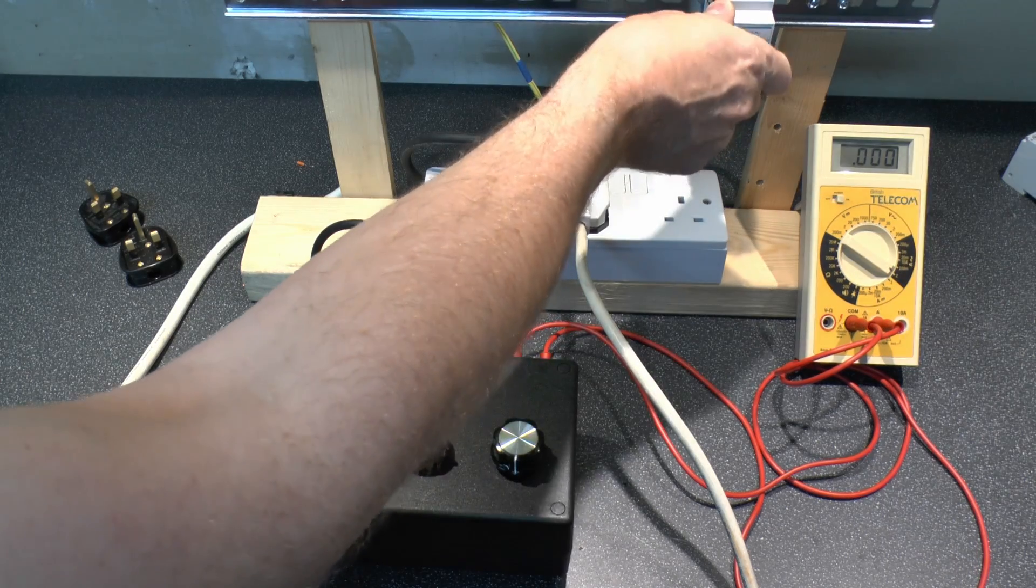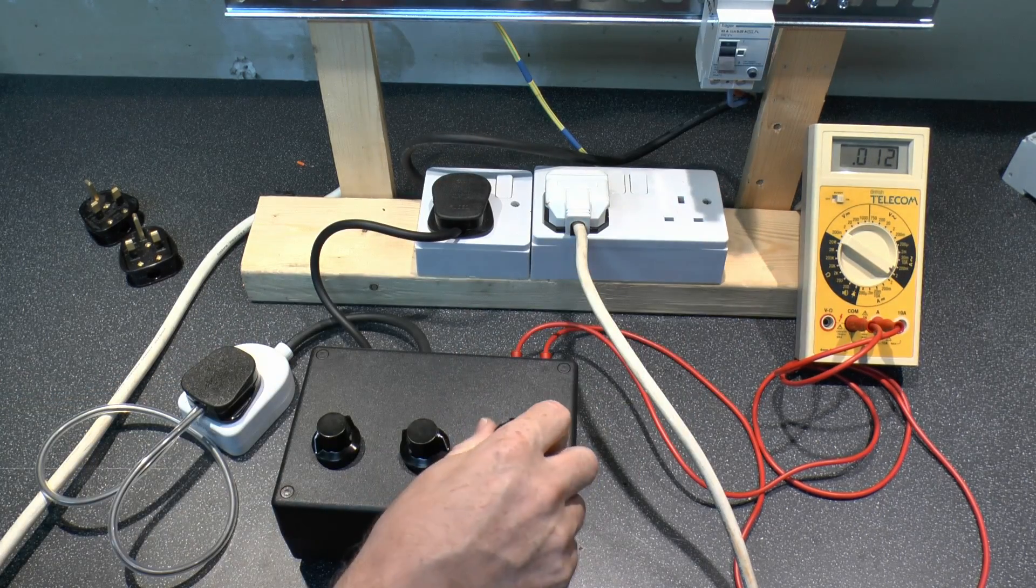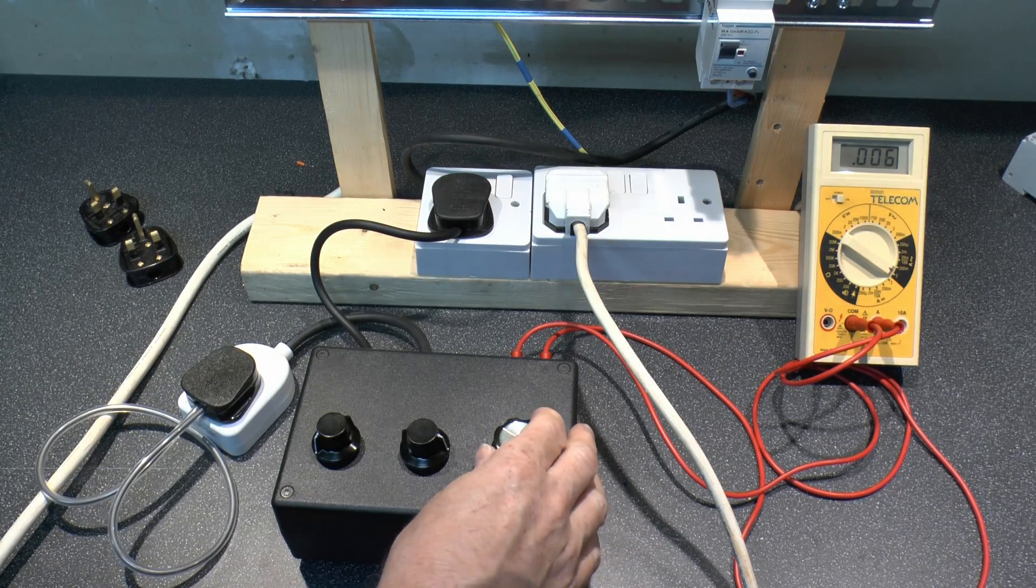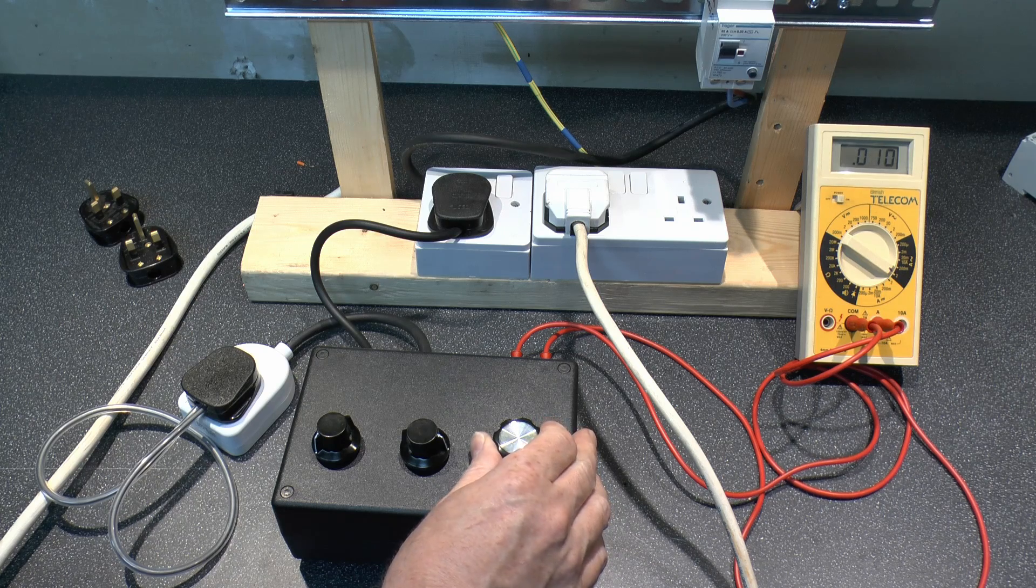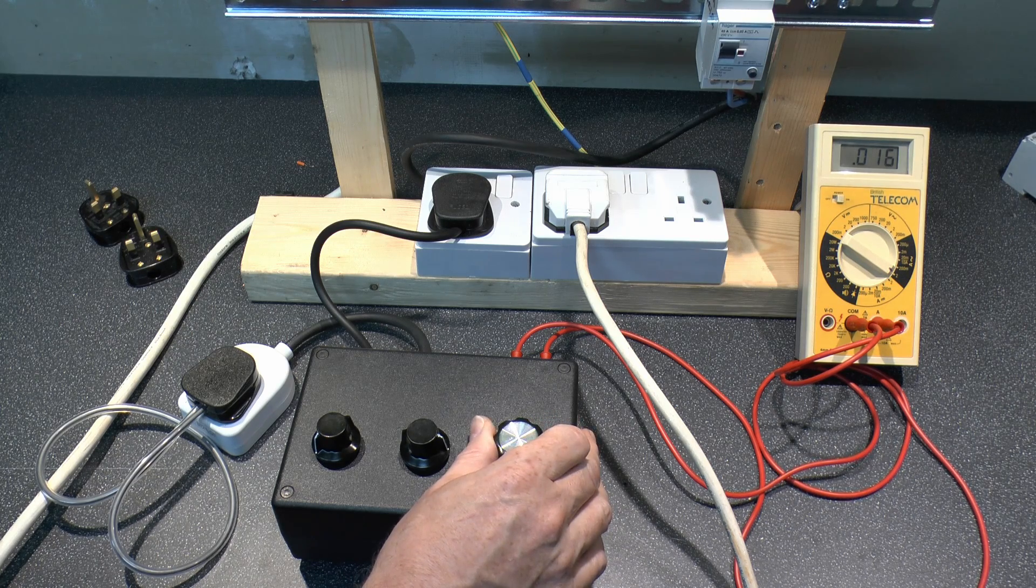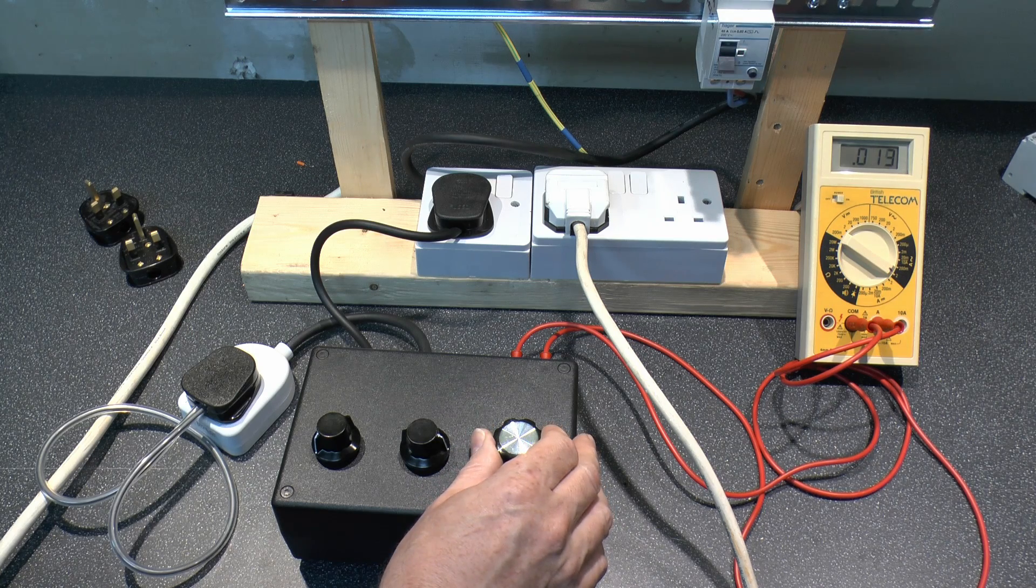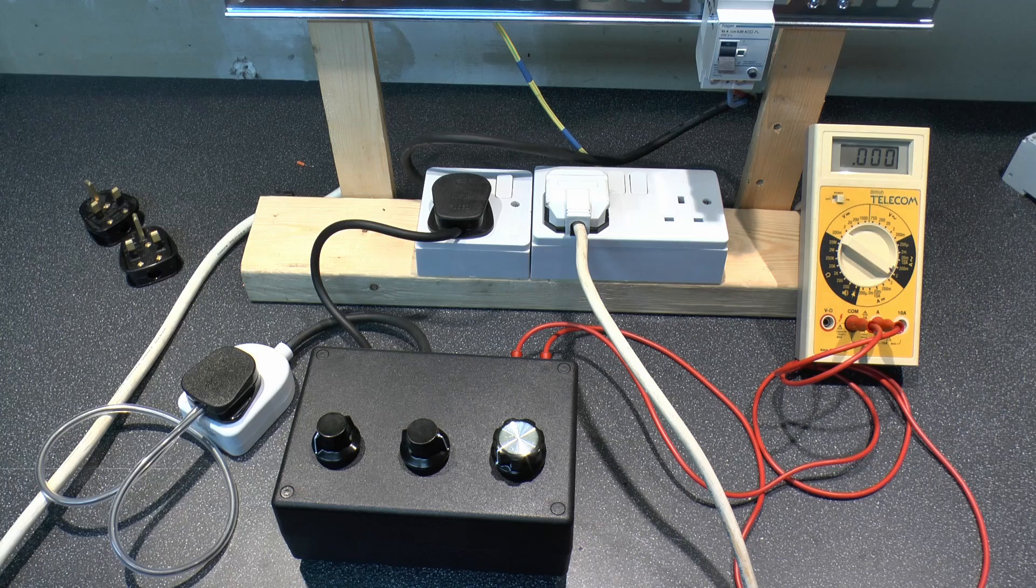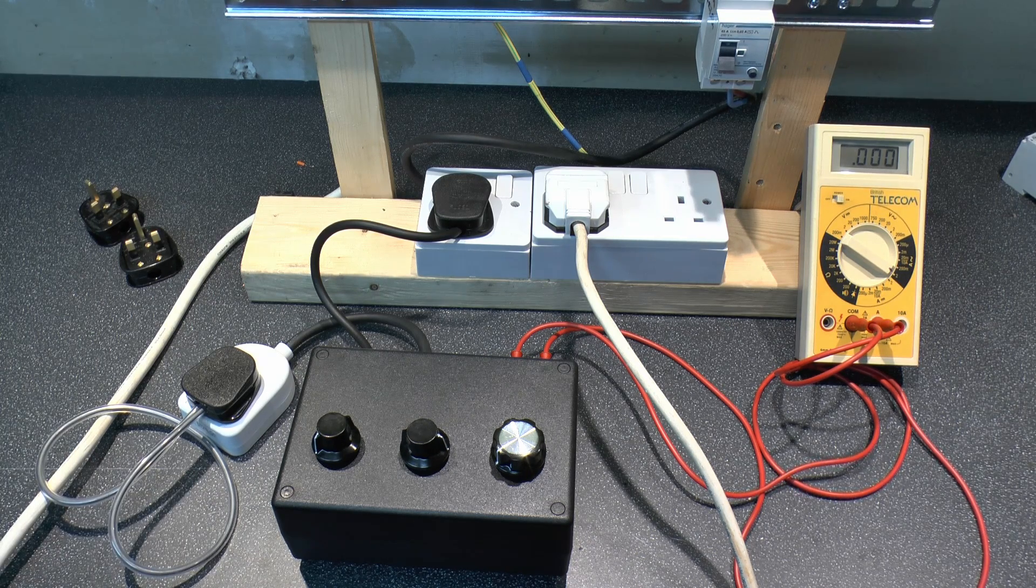If we try and reset that then it will trip straight away just turn the current back a bit. So again let me just try that again just slowly increase the current there. Yep so just about 19 or 20 there so fairly consistent with what we had previously. Just ready to confirm that what we've got here is actually working as intended.